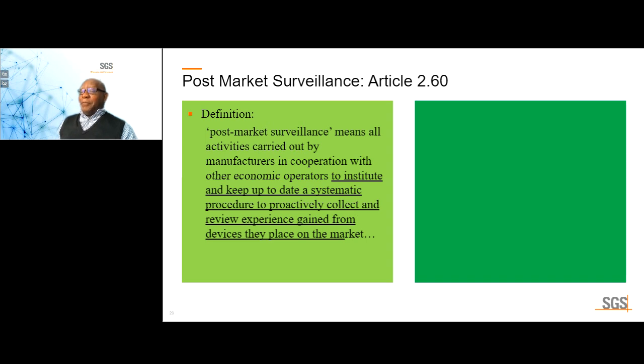Reactive, as the name suggests, is manufacturer reacts following some incident. So it could be a product complaint. It could be a vigilance that has been reported to the competent authorities. But with proactive PMS, the authorities expect manufacturers to go out into the market and gain some information about their device in the real world. Because before going to market, we make certain assumptions about our device. We probably leverage from past experience, tweak the design, and come up with an amended or a new design. That's okay. But when you are now in the marketplace, do you get the expected results?